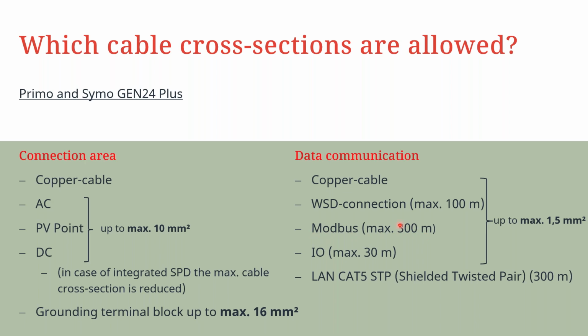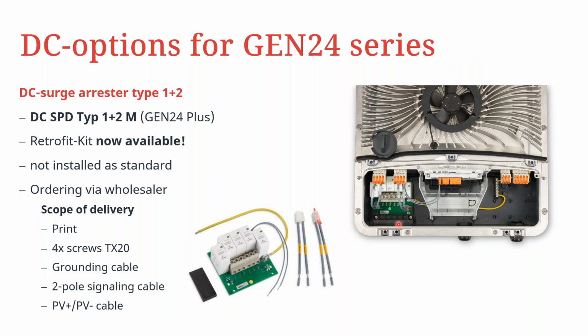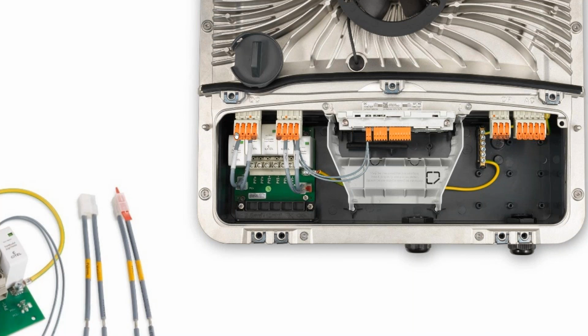The GEN24 Plus also comes with some options on the DC side, related to OVPs or surge arresters. Here you can get the Type 1+2, but this is only available as a retrofit kit, so it is not installed as a standard component when the inverter is produced. Here we can see how the SPD is fitted and how the cross section of the cables would be affected on the DC side. Once you fit the SPDs, there will be some restriction on the maximum size of the cable that can be used on the DC side.